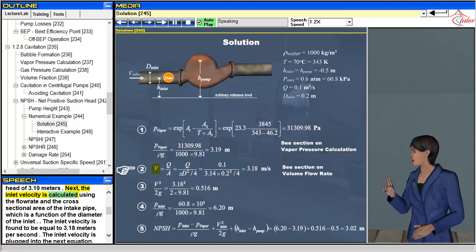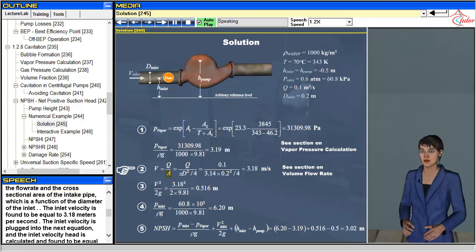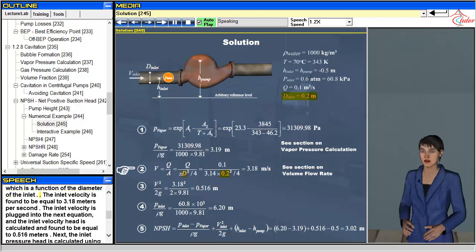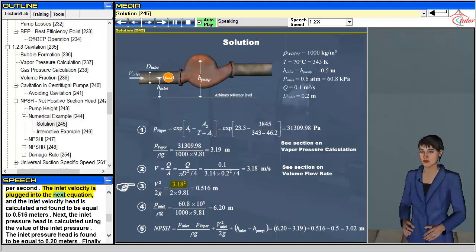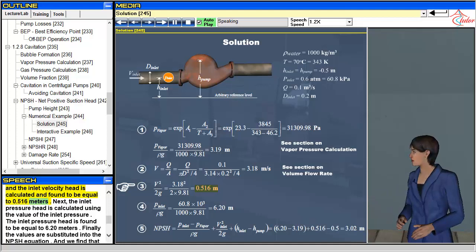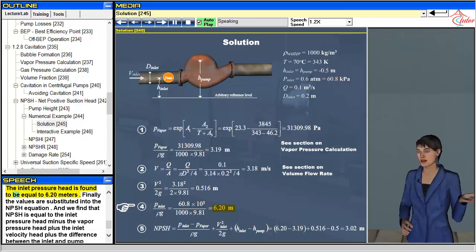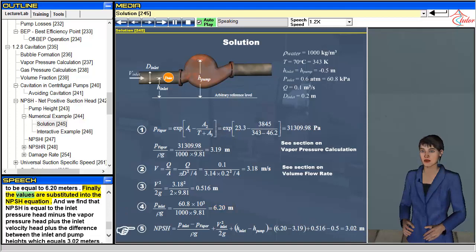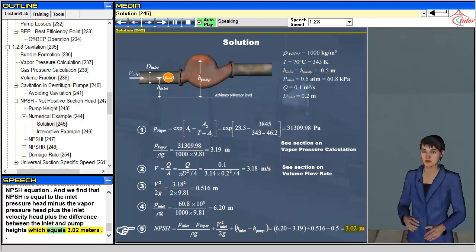Next, the inlet velocity is calculated using the flow rate and the cross-sectional area of the intake pipe, which is a function of the diameter of the inlet. The inlet velocity is found to be equal to 3.18 meters per second. The inlet velocity head is then calculated and found to be equal to 0.516 meters. The inlet pressure head is calculated using the value of the inlet pressure and found to be equal to 6.20 meters. Finally, the values are substituted into the NPSH equation: NPSH equals the inlet pressure head minus the vapor pressure head, plus the inlet velocity head, plus the difference between the inlet and pump heights, which equals 3.02 meters.